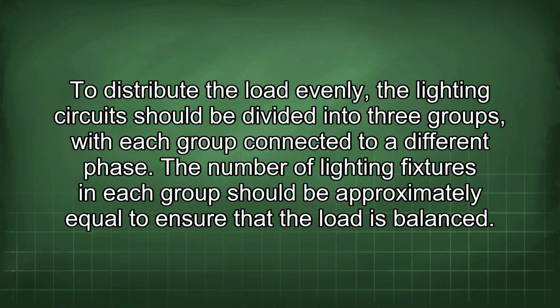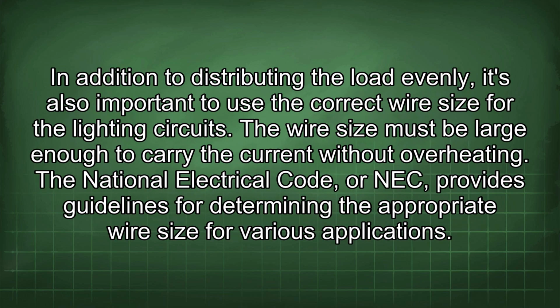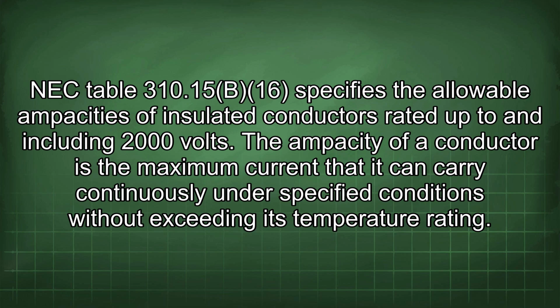In addition to distributing the load evenly, it's also important to use the correct wire size for the lighting circuits. The wire size must be large enough to carry the current without overheating. The National Electrical Code, or NEC, provides guidelines for determining the appropriate wire size for various applications. NEC Table 310.15(B)(16) specifies the allowable ampacities of insulated conductors rated up to and including 2000 volts.